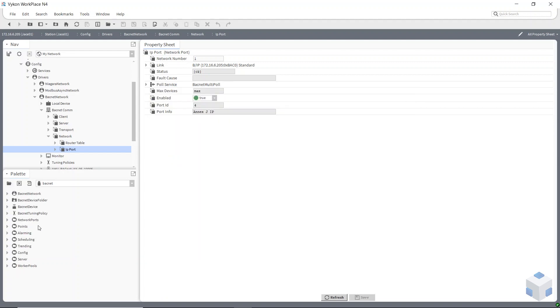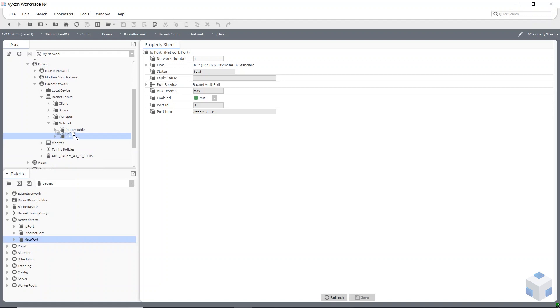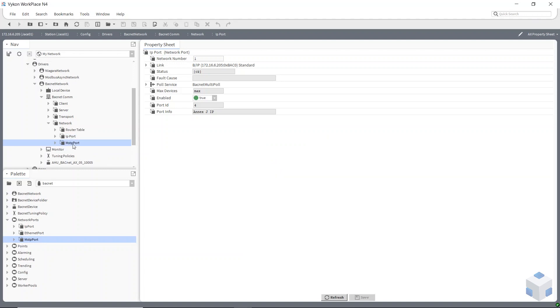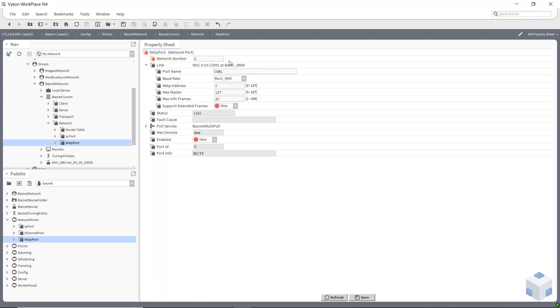So to set up a 485 I just add another network. So if I open up my palette for my BACnet, down here we've got network ports. So you've got three different types you can add there. You can only have one IP port but I can add MSTP ports to this. And to do it you just drag it on your nav sidebar, release it on top of network, and then you can just go ahead then and configure your MSTP settings. So you'd have to go and select your com port that you're using, your baud rate, etc. to set that up. So that's where you go to add your MSTP ports.